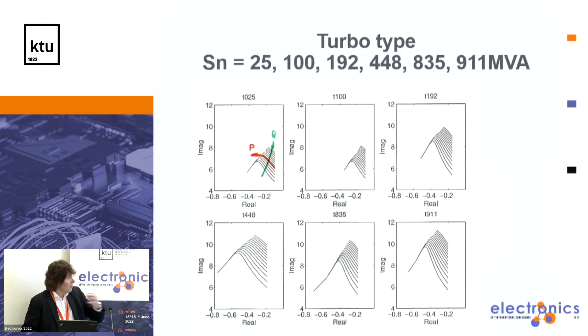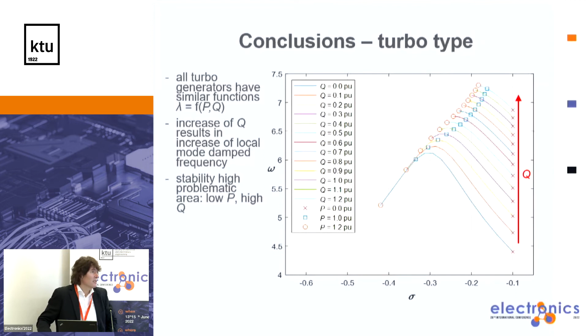Our conclusions for this type: again, all turbo type generators have similar dependencies of eigenvalues on P and Q. By increase of Q, the conclusion is the same - higher reactive power means higher frequency. But it is not possible to say what will increase the damping of the local mode oscillation system.